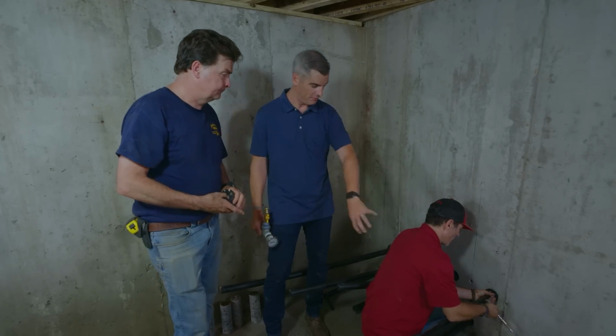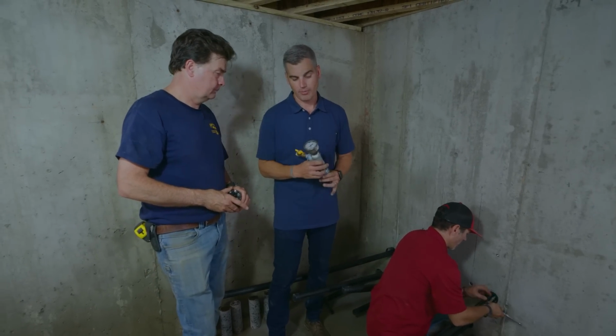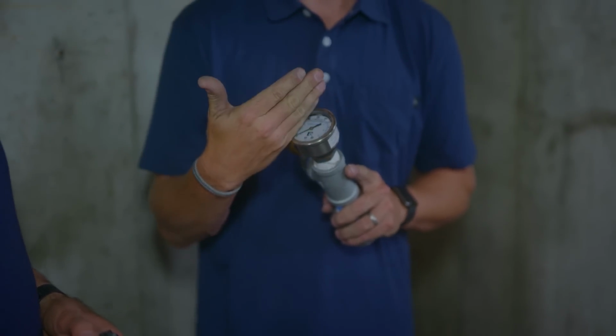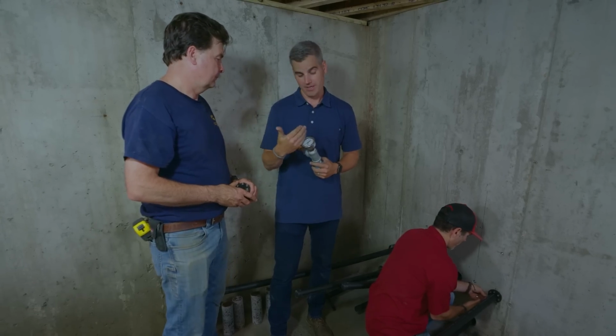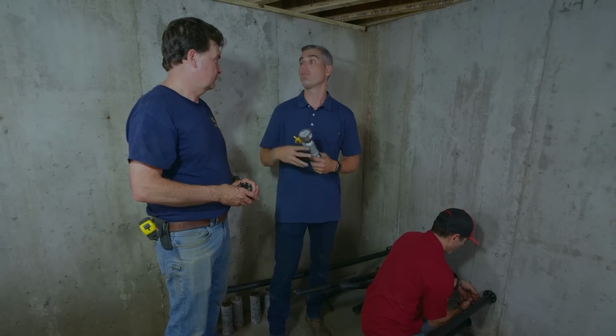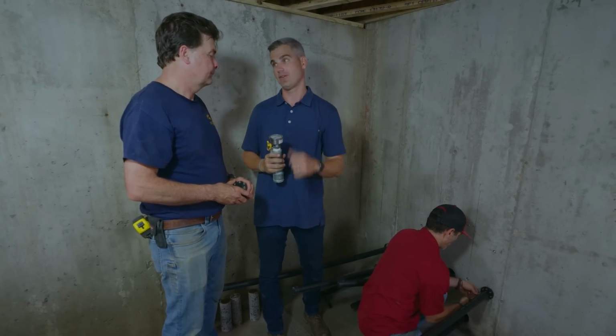After that, they're gonna fill the system with water. They'll hook up a pressure gauge like this and bring it up to 70 PSI pressure. They want to make sure we don't have a leak, that it's not gonna drop. On top of that, they're gonna watch it over time before it gets backfilled, because now's the time to fix the leak. Smart idea.